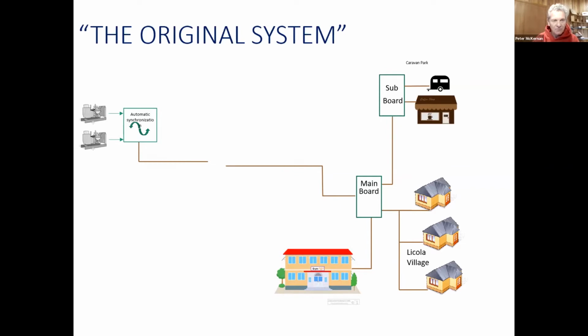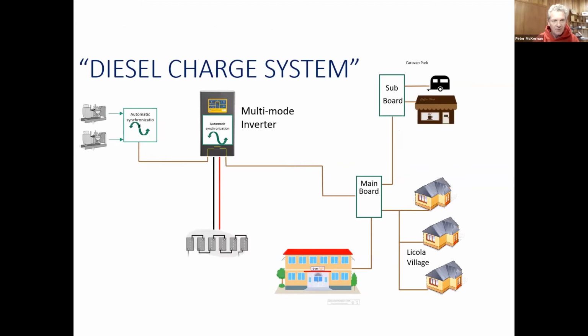The first thing we did was interrupt that circuit and install a multi-mode inverter and some batteries. This is what we call a diesel charge system. How it works is the energy can flow through the inverters, but any excess capacity inside the generators is put into the batteries. Once the batteries are full, we turn the generator off, and then we use the energy in the batteries to run the site.